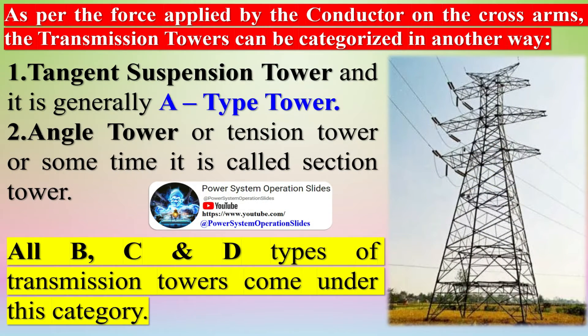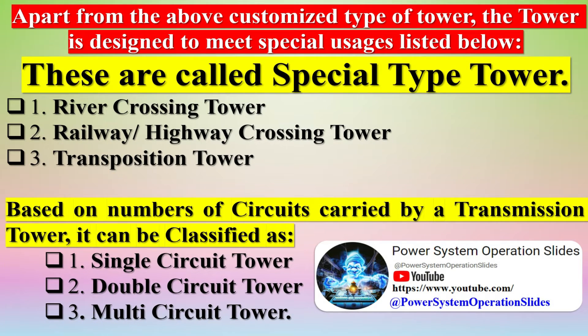As per the force applied by the conductor on the cross arms, transmission towers can be categorized as: tangent suspension towers, generally called A-type towers; and angle towers, or tension towers, sometimes called section towers — B, C, and D types fall under this category. Apart from these, customized towers are designed for special uses like river crossing towers, railway/highway crossing towers, and transposition towers.